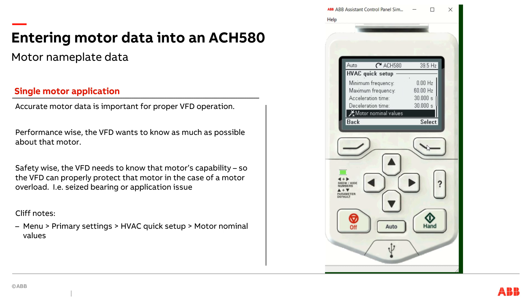So there you go — we just set up the ACH 580 based on the motor nameplate information. This drive is now ready to properly control and protect this motor. One of the key reasons to enter nameplate data correctly is so the VFD can safely protect the motor. It needs to know how many amps the motor is rated at, so if the motor gets into an overload situation — whether it's a bearing seizing up or something jamming the application — the drive can trip offline if it sees the motor drawing too much current for too long.